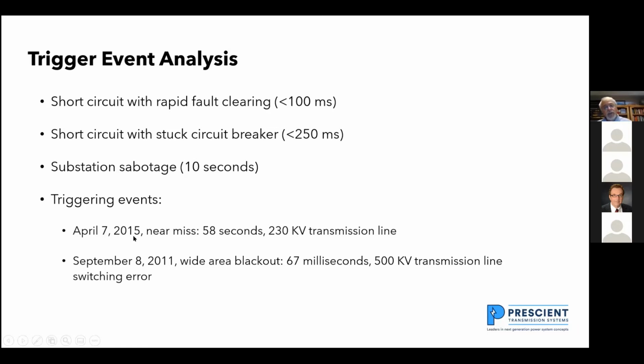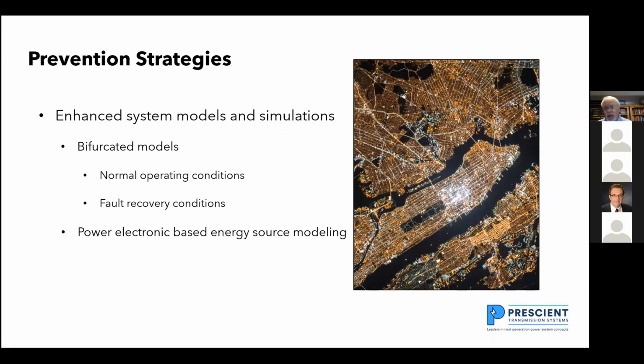On April 7th of 2015, there was a near miss. There was a three-phase fault on a 230 kV transmission line that persisted for 58 seconds. The only reason this didn't progress to a wide area blackout is that it happened in April. If the same condition had occurred in July instead of April, we would have had a major blackout. And on September 8th, 2011, they did have a wide area blackout. The short circuit that initiated the event was cleared in 67 milliseconds, and it turned out to be a 500 kV line fault caused by a switching error. So the times we look at are tied to events that we've investigated on the power grid.